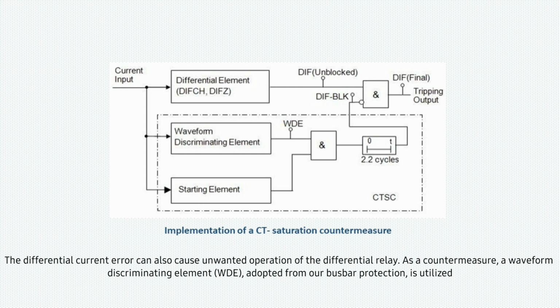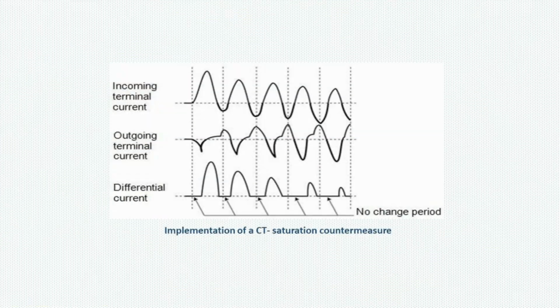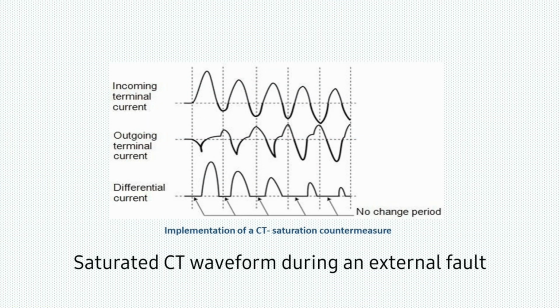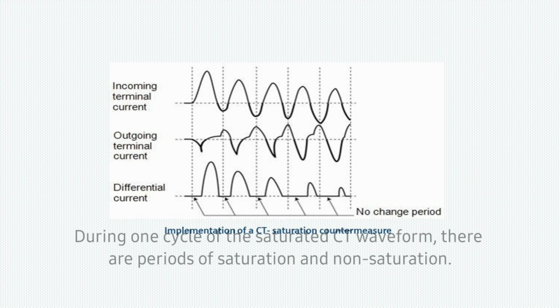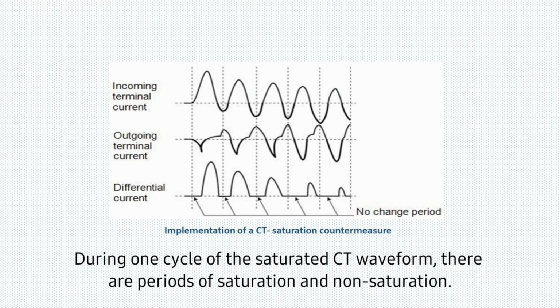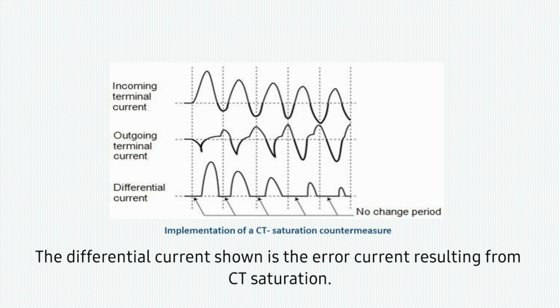As a countermeasure, a waveform discriminating element WDE adapted from our busbar protection is utilized. The second figure shows an example of a saturated CT waveform during an external fault. During one cycle of the saturated CT waveform, there are periods of saturation and non-saturation. The differential current shown is the error current resulting from CT saturation.